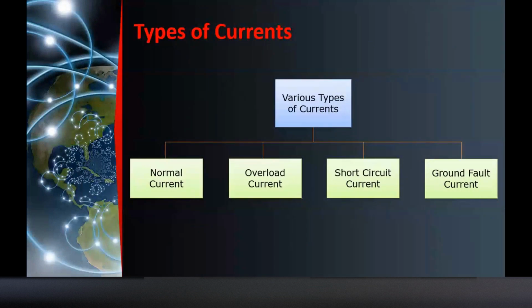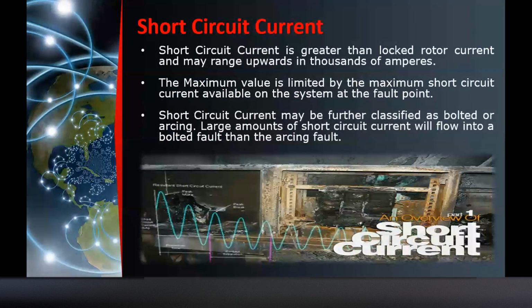So type of currents. So we have various types of current. We have normal operation, yan yung normal operation of every equipment. So walang problema. We have overload current, short circuit current, and ground fault current. Okay? So short circuit current, pag sinabi natin short circuit current, is greater than the locked rotor current and may range upwards in thousands of amperes. Kaya nga mapapansin nyo class, lahat ng circuit breaker is in thousands. Kaya nga naka-kilo ampere interrupting capacity. So for example, 10 kAIC, that is 10,000 amperes.